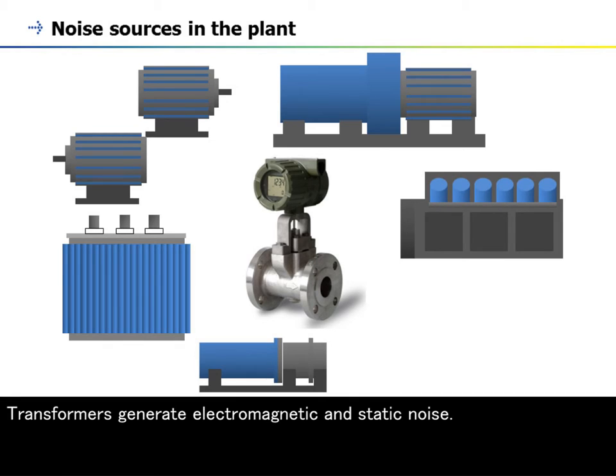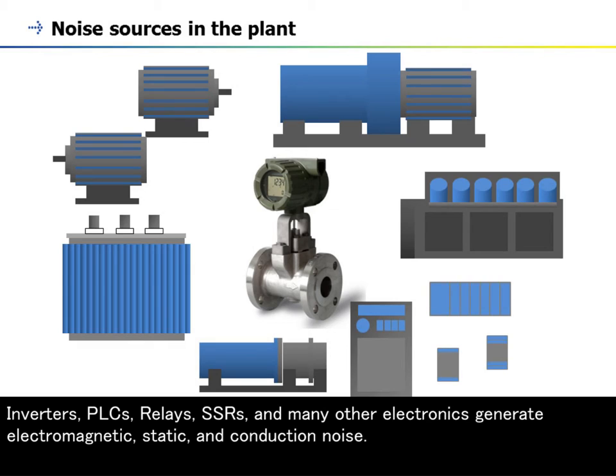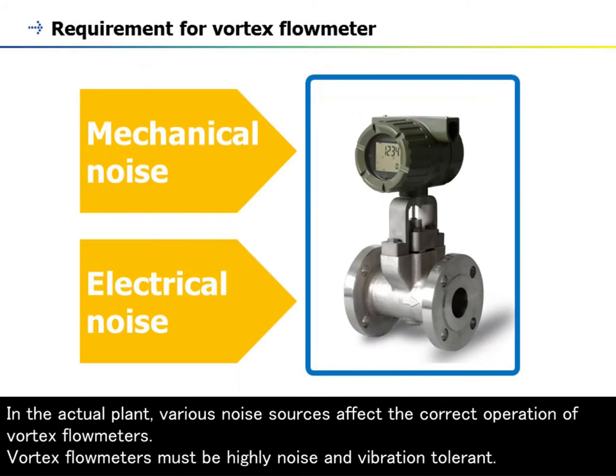Transformers generate electromagnetic and static noise. Inverters, PLCs, relays, SSRs, and many other electronics generate electromagnetic, static, and conduction noise. In the actual plant, various noise sources affect the correct operation of vortex flow meters.